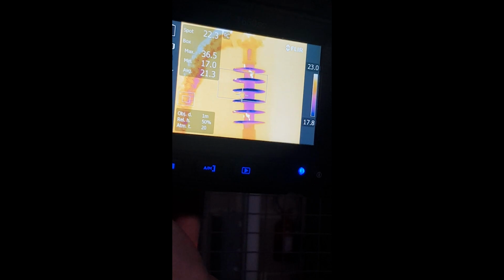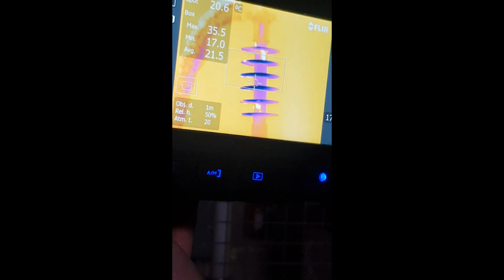Now we'll go and see it on the IR camera. See here, the arcing can now be easily detected because it increases the temperature. And you can see it here on the surface. Whenever there is an arc here, the temperature will increase. And this is how you can detect dry band arcing using the IR camera.